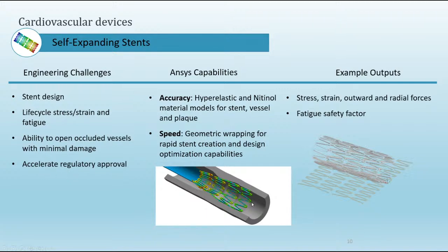The stent shape is also important. There's a lot of these turns because it's pretty much a very complicated spring. If during the processing stage the stents are not designed properly, some of these tips could tip up, and that could cause the stent to dig into the vessel. So you don't want to have too much stress concentrations in the blood vessel, right?